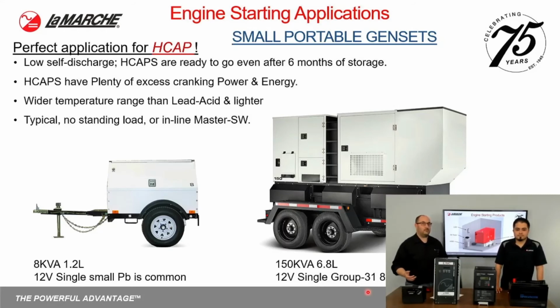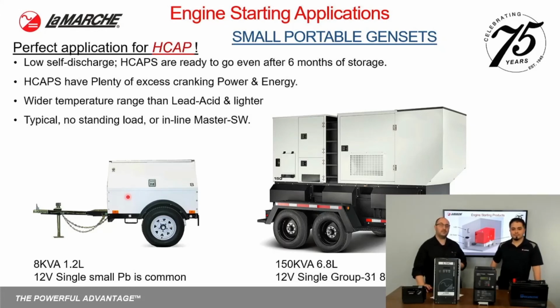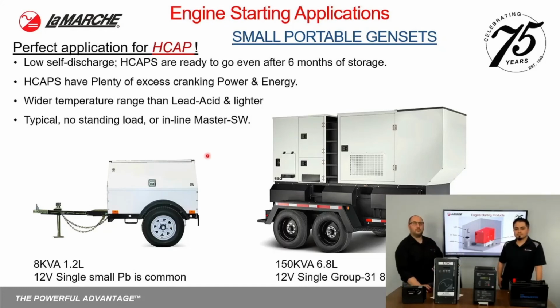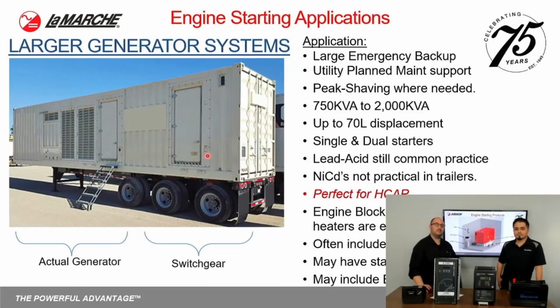That's not a good application for an EDLC or even for some of the lead acid batteries that have higher self-discharge. But an HCAP, that has such a low self-discharge that would perfectly fit this application, even with several months of sitting idle in a parking lot waiting to be utilized. So it's a really good fit for small portable gensets.